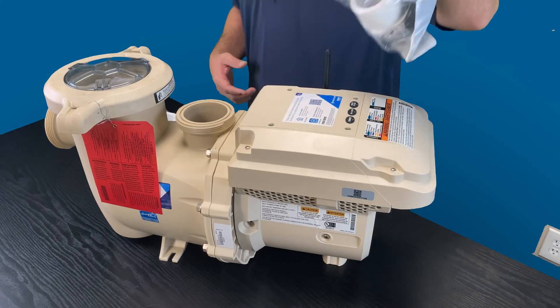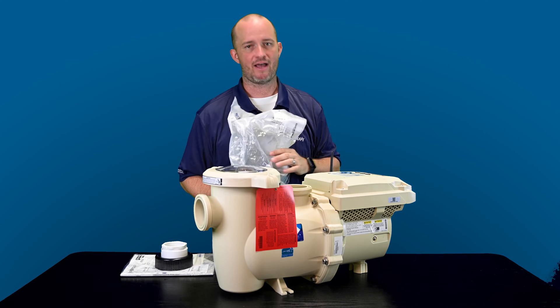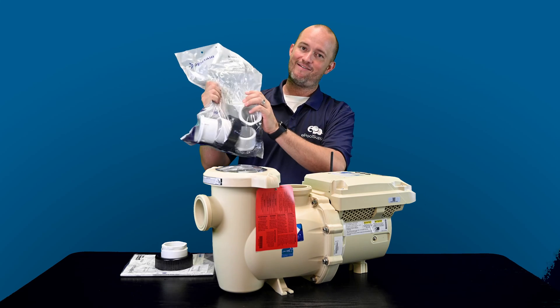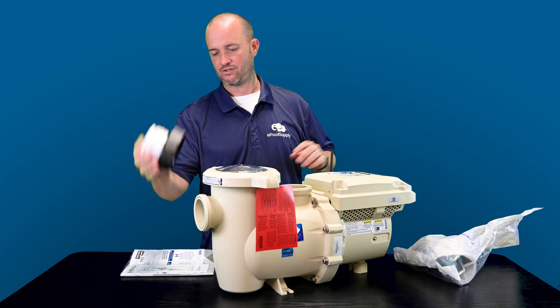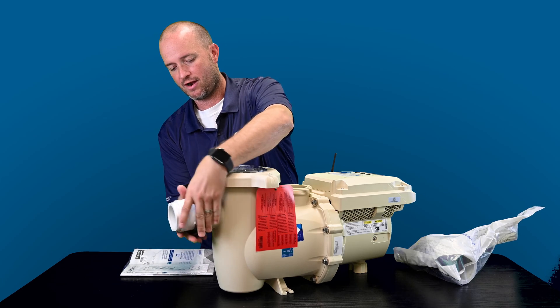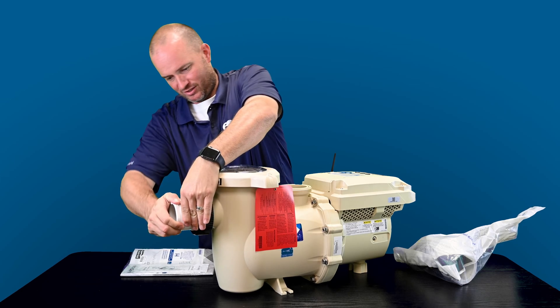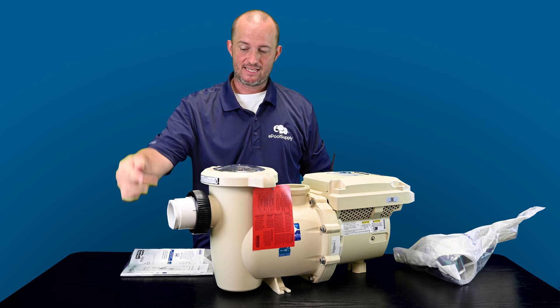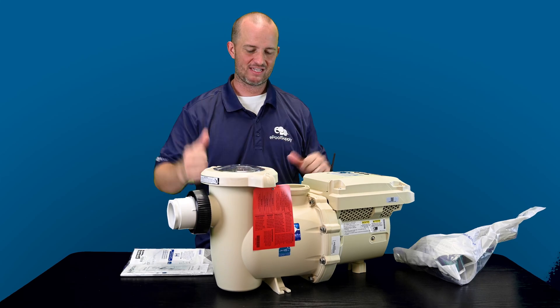It comes with a union kit. A lot of people over the years have been like, hey, I don't want to use my threaded nipples anymore on the inlet of my IntelliFlo. People bought aftermarket unions to make it work — they finally gave a union kit. It comes with two unions, front and top. I have one that's already open, and it literally just threads on with an O-ring. Two and a half inch on the inside, but they give you the two and a half to two inch reducer right here. So if you only have two inch pipe coming in, they give you the reducer in the box, which is fantastic.